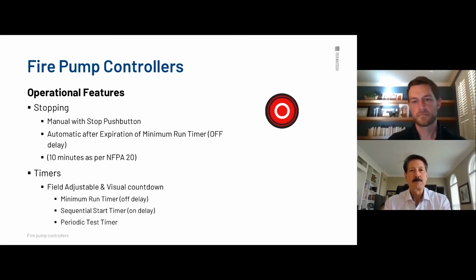Stopping it manually with the stop push button is great, but you would have one other option, and that's the flange mounted operator itself. You can literally pull that down and cut power to the whole device itself. So that is another stopping device that we really didn't touch base on, but to me, that's the one I use when I'm out in the field if something like that does occur. Yeah, that's true. If you have something like that happening, you can always kill the power. That definitely is a method of stopping.